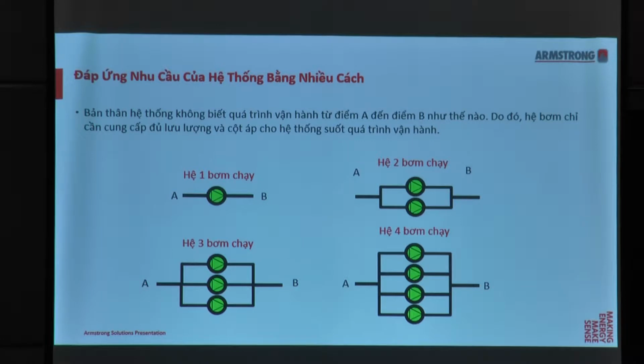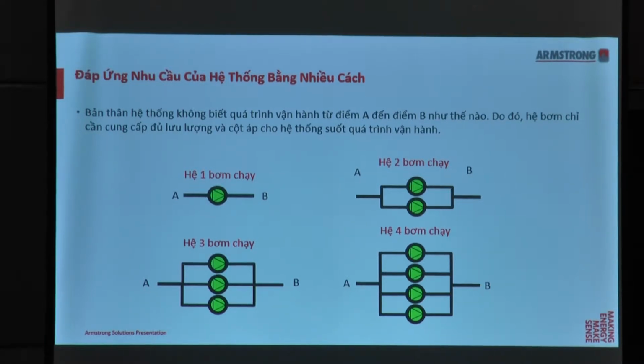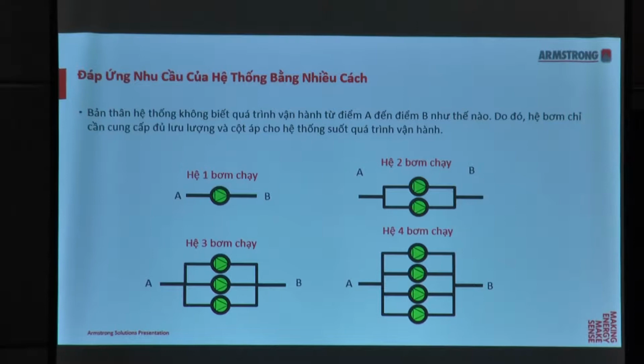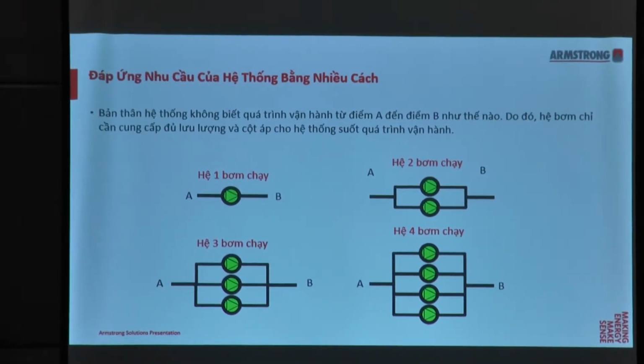Now, let's consider you are trying to deliver the fluid from point A to point B. What these diagrams are trying to say is that so long as you're delivering the right flow and the right head, the system doesn't care how you deliver it or in what kind of configuration. So you can choose one pump on duty, 2 pumps on duty, 3 pumps on duty, or 4 pumps on duty. Regardless, it still gives you the required head and flow.